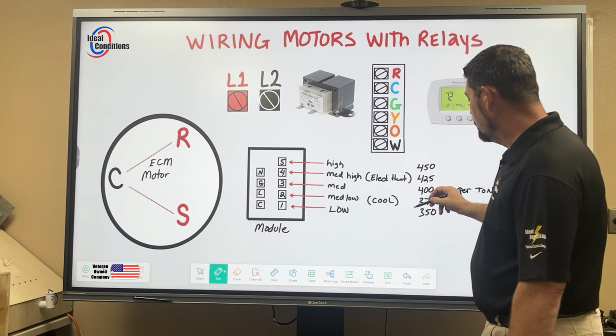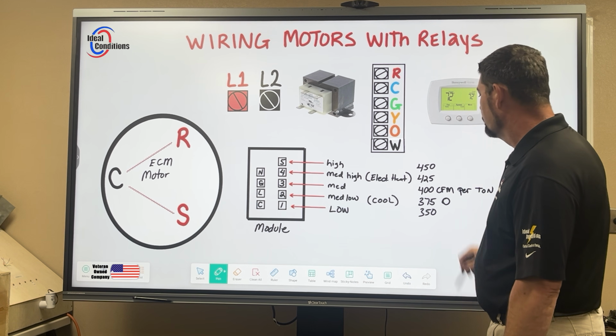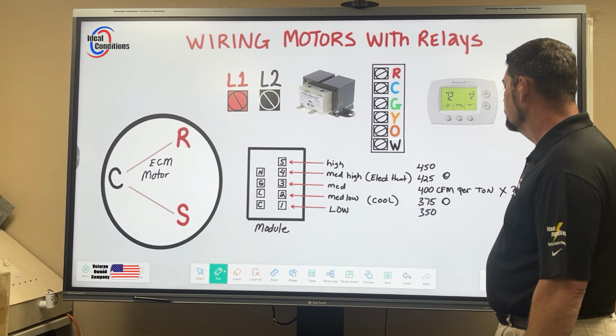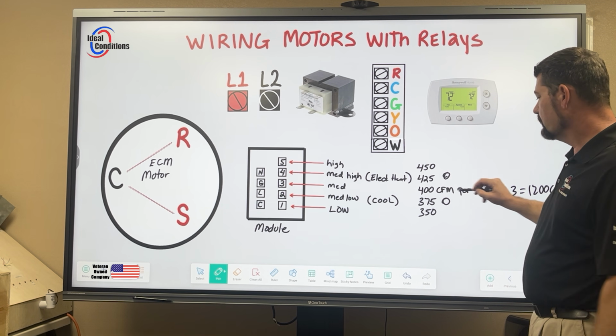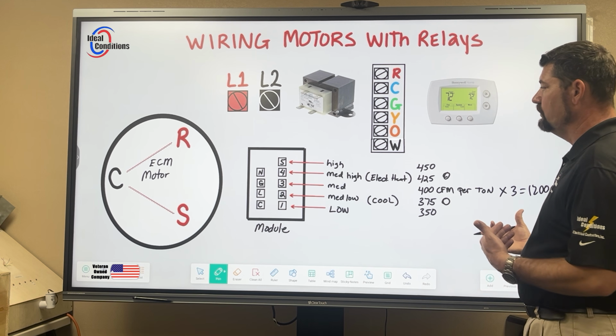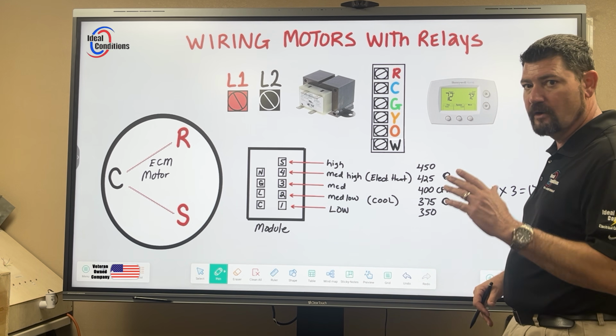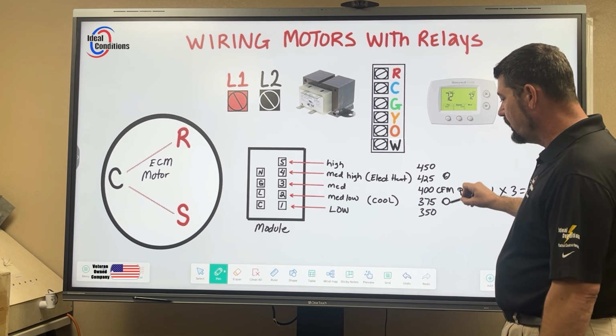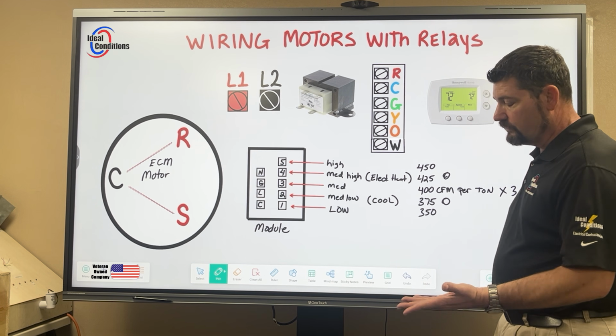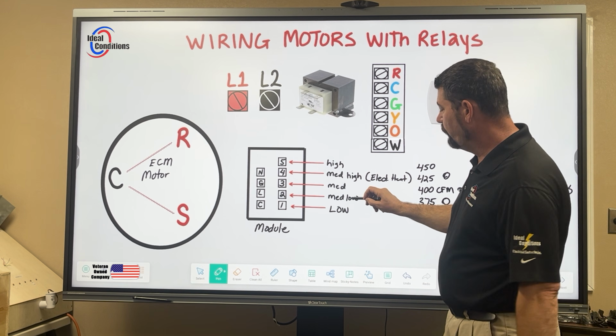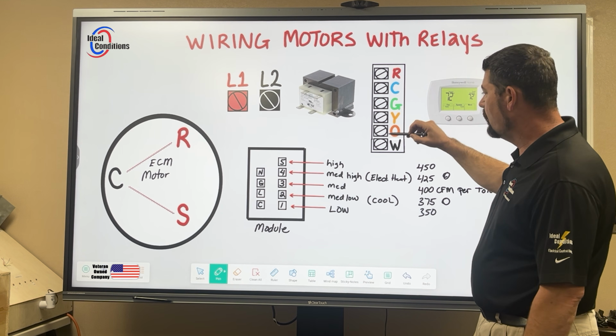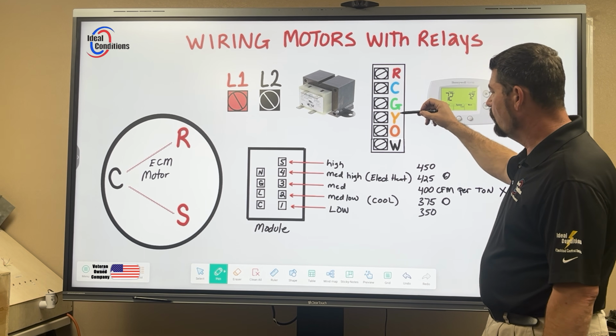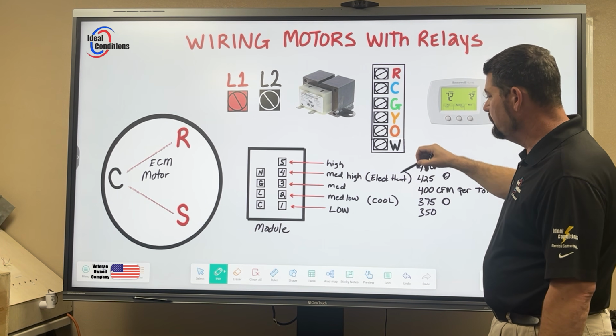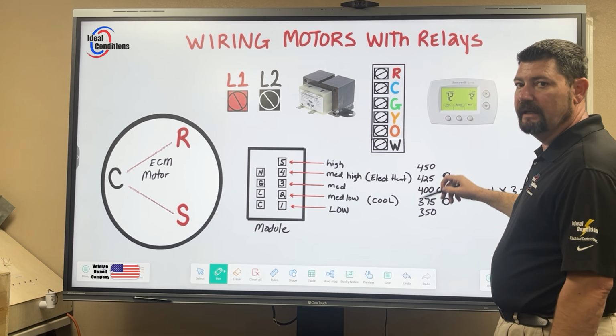And so they come wired up on medium low and medium high, right? And so as you can see here, 400 CFMs per ton is the typical speed that you would normally operate on if you're just dealing with a PSC motor and you're only running 1 speed and that's it. Here they allow you to have those 2 speeds. So I'm getting more comfort with the ECM because I can run 2 different speeds. You're not running them both at the same time, but I can run this for my fan call anytime I get a Y call or a Y and an O call. But if I'm getting a Y and an O call with a W call, then that's just not enough CFMs. I need to pick up those CFMs.